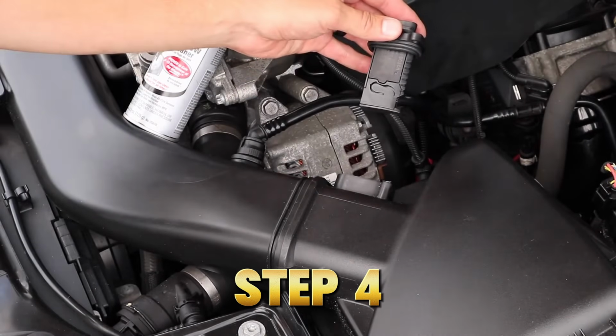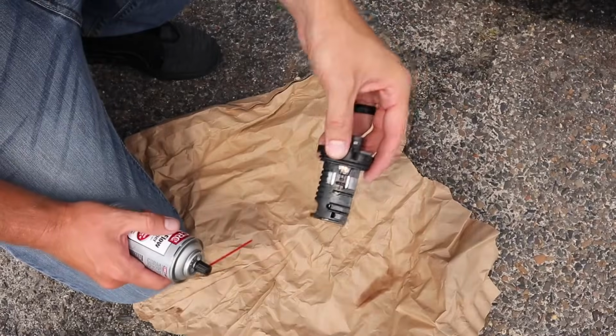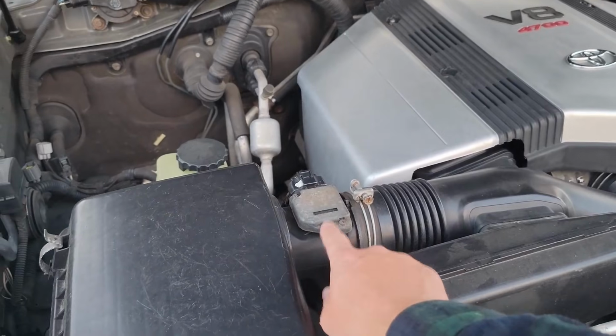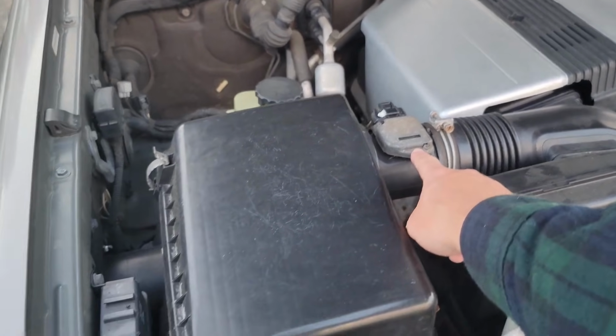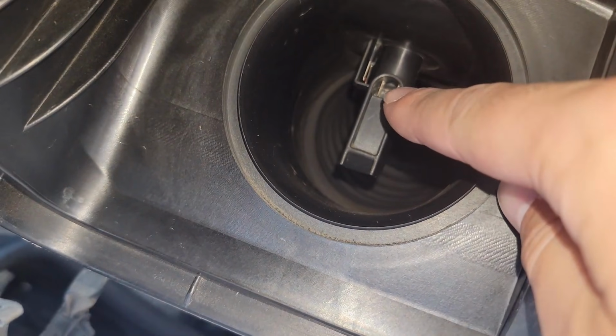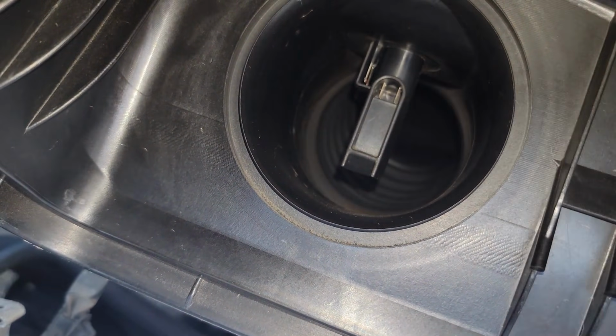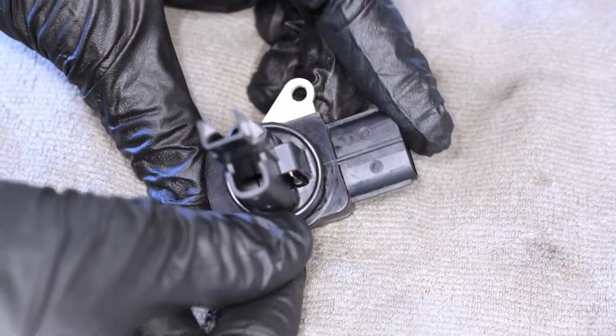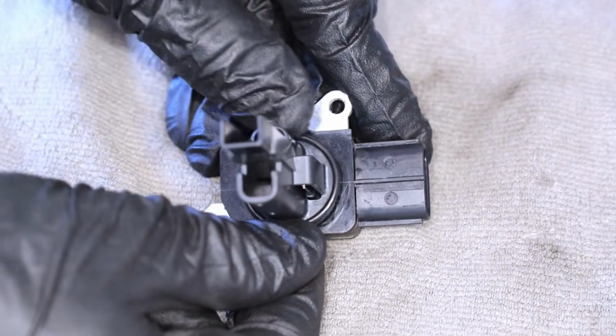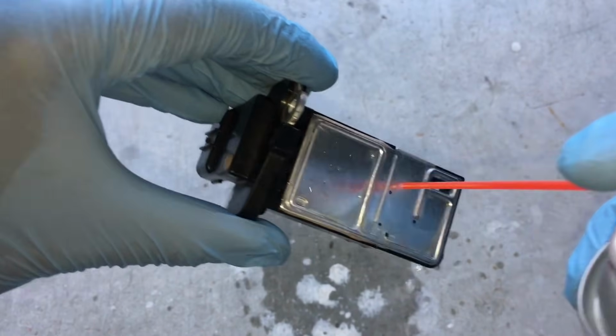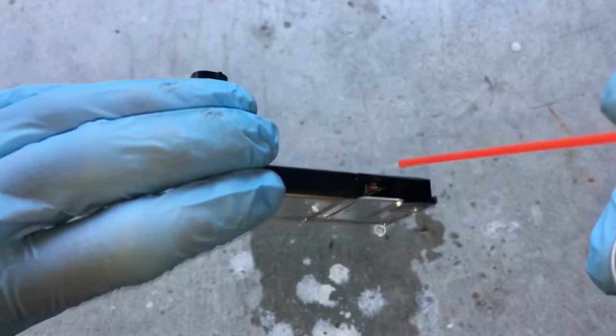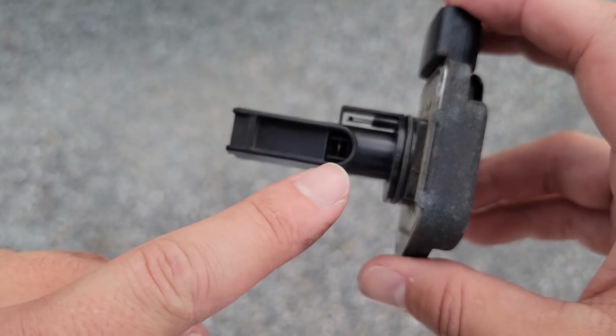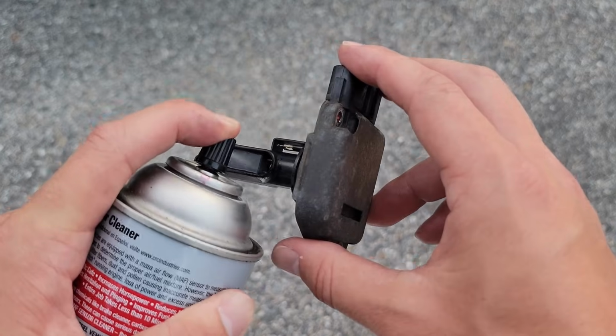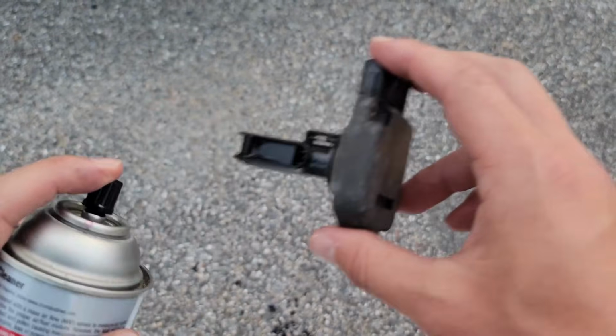Step 4. Never touch the sensor element. This deserves repeating. Inside the sensor, a hair-thin wire or film measures airflow. If you touch it, calibration is ruined. The sensor is permanently damaged. Cleaning means spraying only. Hold the can several inches away and let the cleaner do the work. No wiping, no brushing, no shaking debris loose.